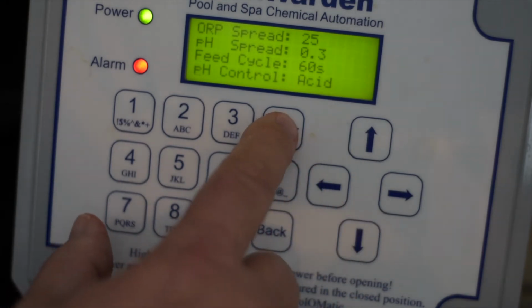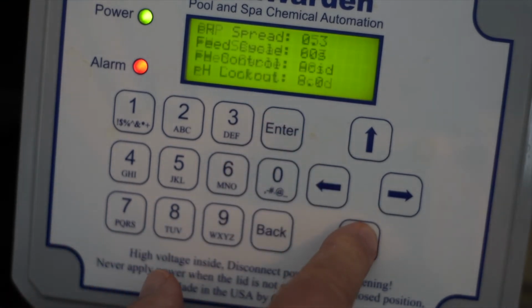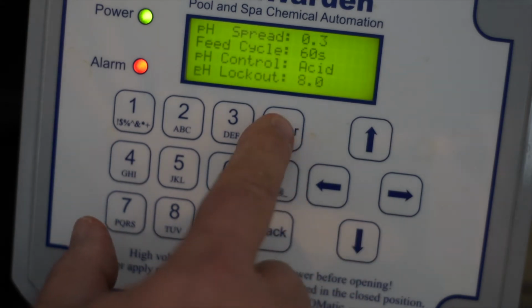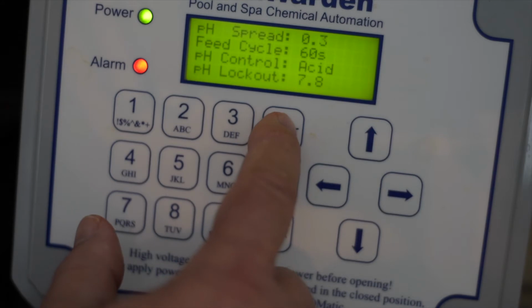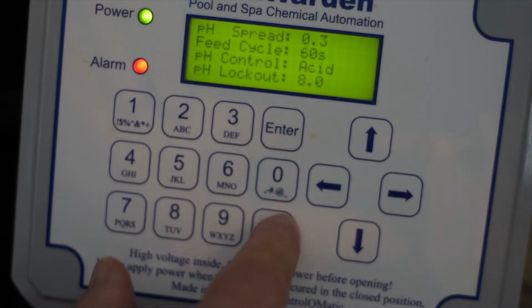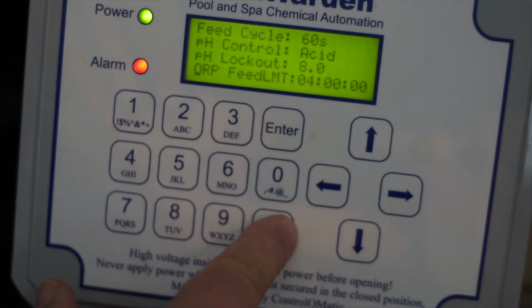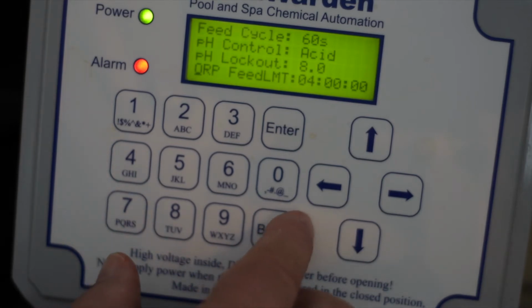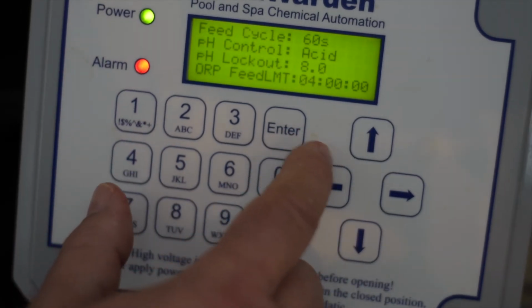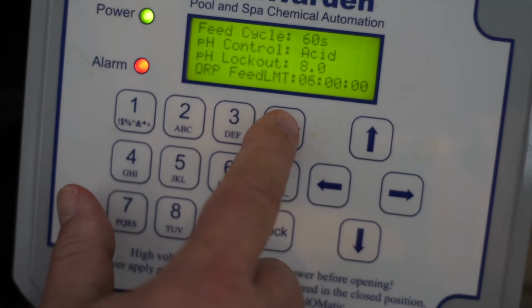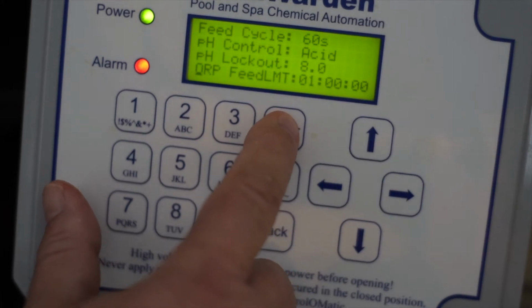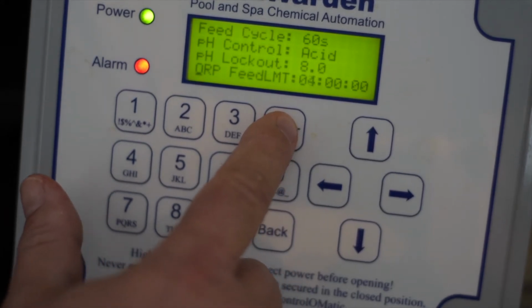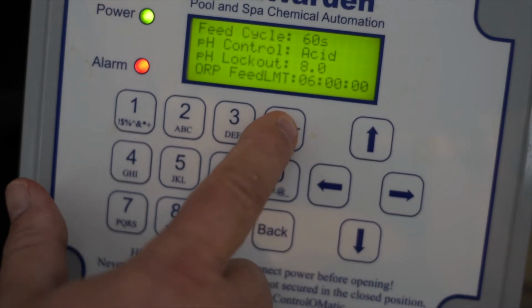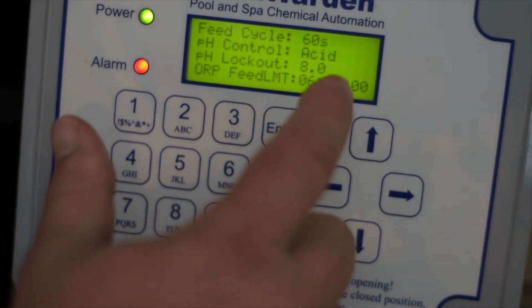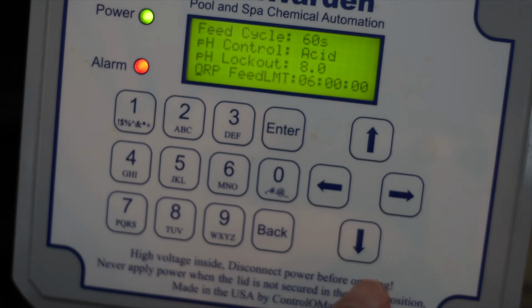And then pH control, acid or base. You can have your pH lockout to off, 7.8, 7.9, or 8.0. ORP feed limit is changeable, so we can go 1 hour, 2 hour, 3 hour, 4 hour, 5 hour, 6 hour. That's a timer.